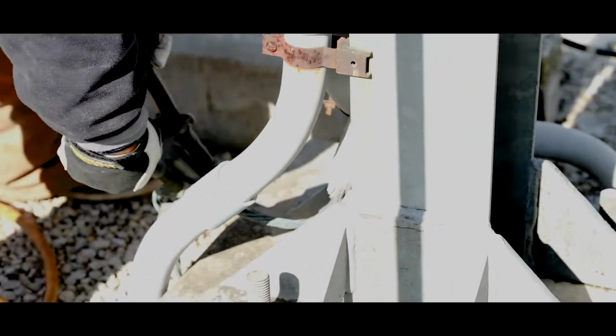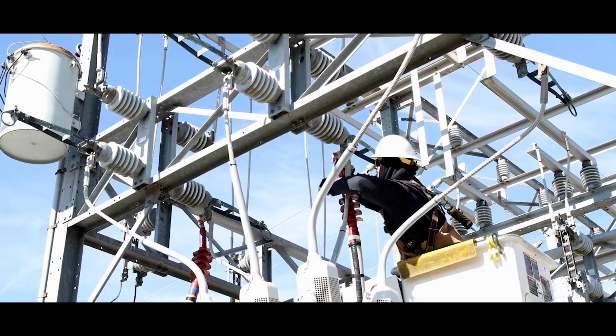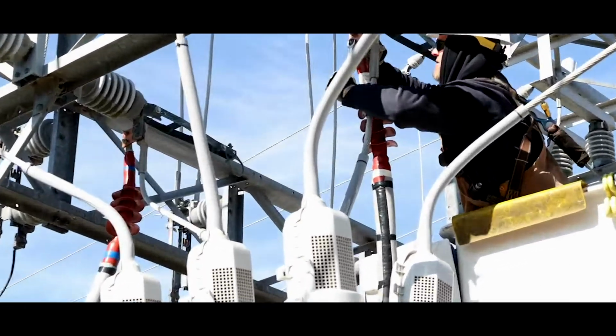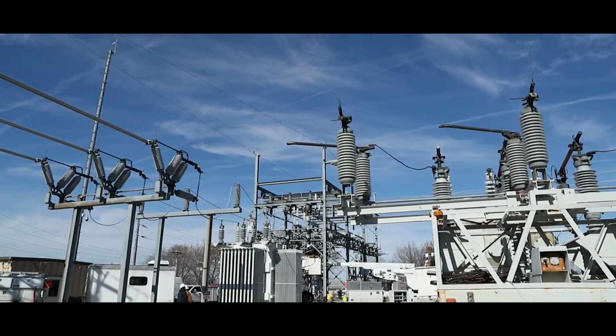Montreal was a great example. They had done a gas test and noted that they had high gas in the tap changer. It turned out there was a minor issue with some connections in there, and they were able to repair those. In that case, we were able to fix a minor issue before it became a major issue or a catastrophic failure. This allows us to do work in a safe manner, respond in a timely manner in emergencies, and do routine maintenance and then put everything back online. Our members never experience any sort of outage or blink or interruption in service.